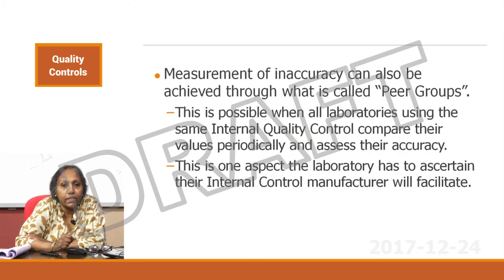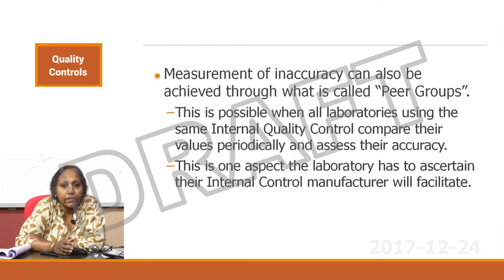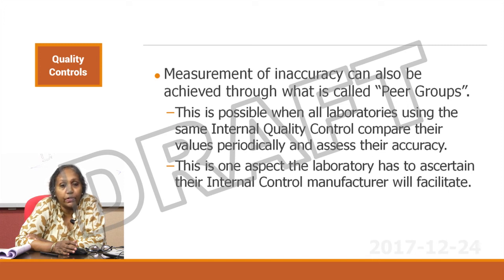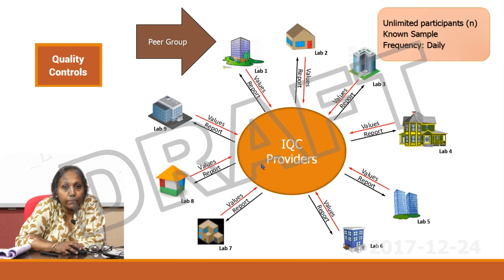Another method of finding inaccuracy using your internal controls is also possible. This system is called the peer group system. In the peer group system, your internal quality control provider enables a mechanism whereby all the users of the internal quality control pool in their results, and periodically their mean values are released, thereby indicating any shift in your accuracy. This is a very robust method because there are many participants and it is a daily process, giving a much more robust estimate of inaccuracies. Therefore, this is one aspect to keep in mind while ordering your internal quality control material — some providers offer this facility and should be given preference.